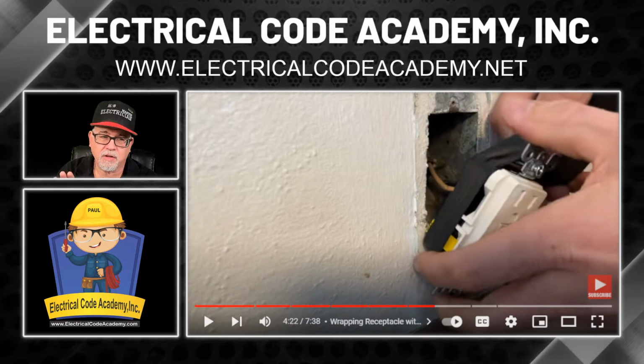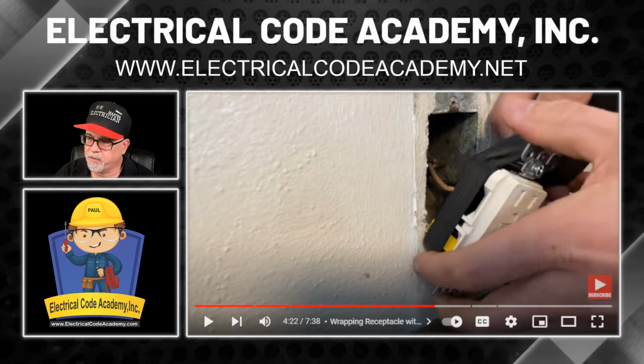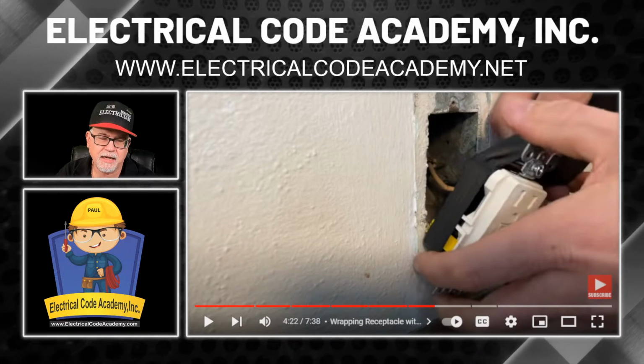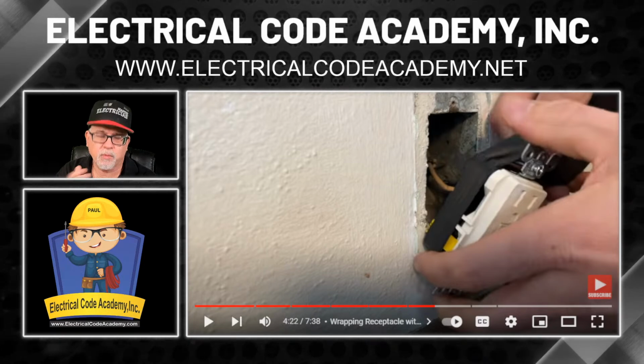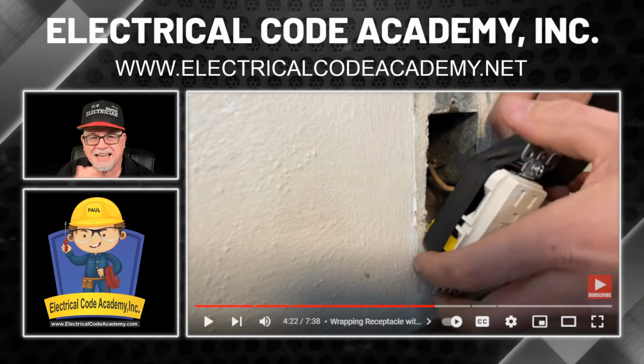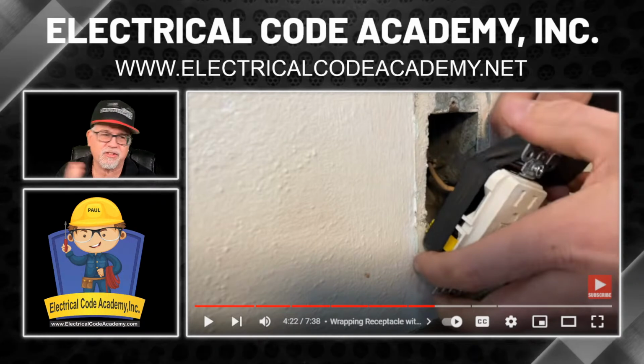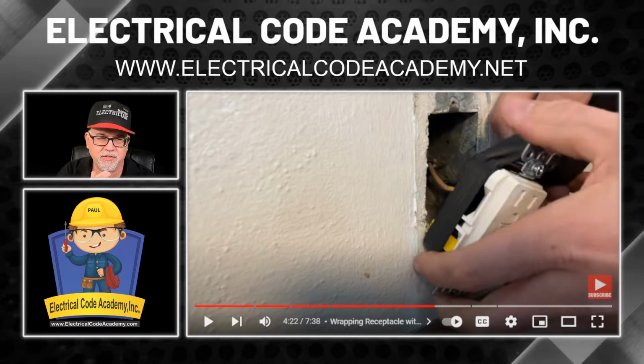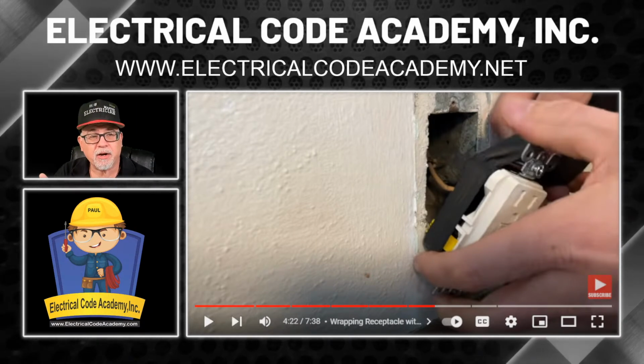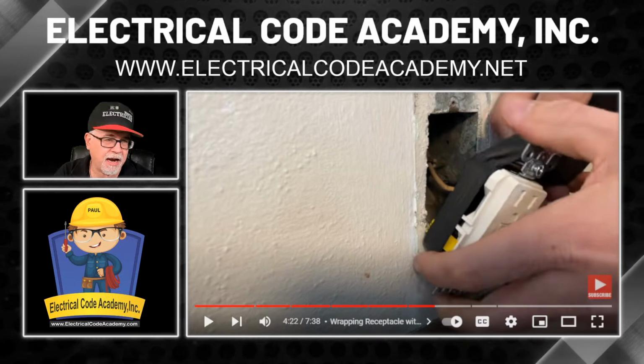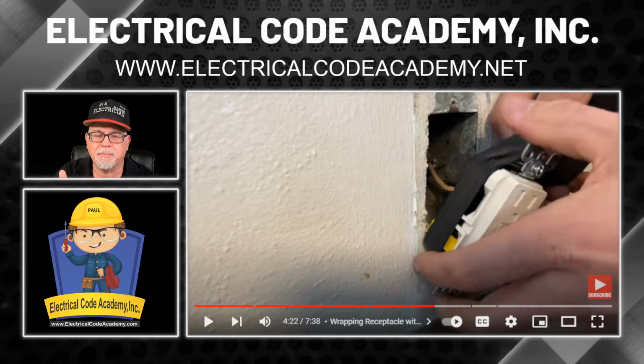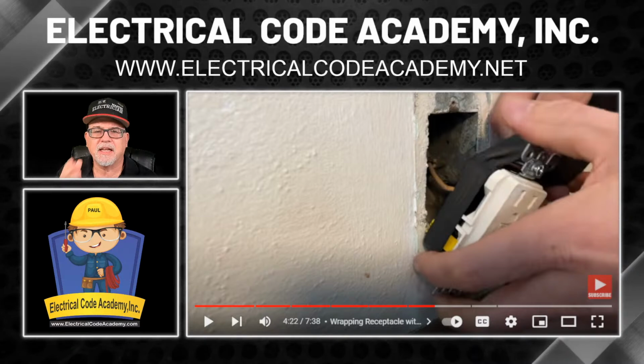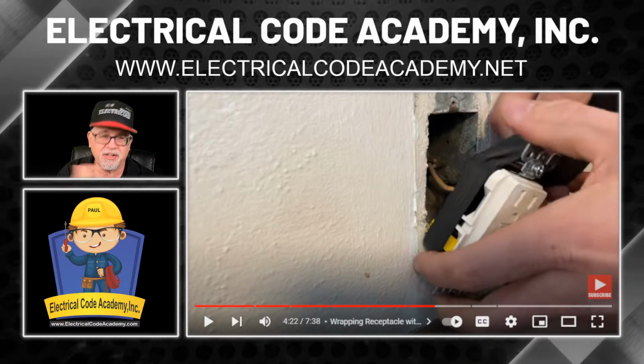So this is not required by code. This is very common. People that work in commercial like to do this a lot. It's actually designed with the mounting screws so that the side of the device could not get to the edge of the box. Again, it is a bigger deal when you have a bunch of equipment grounds in a box and you're tucking everything back in the box, and I get it. But it's really designed so it should not touch the side.